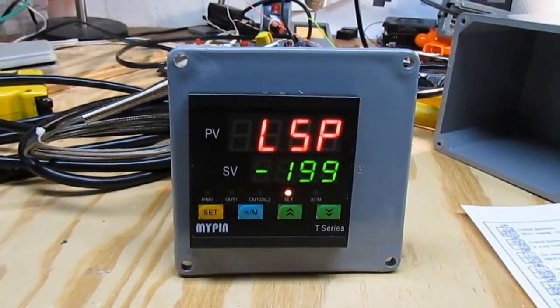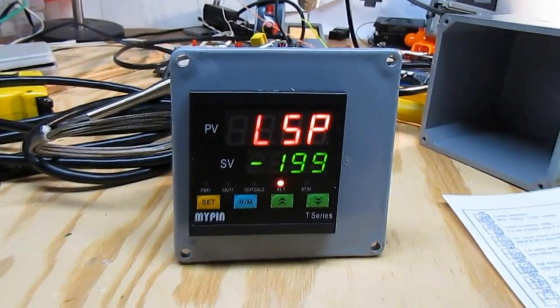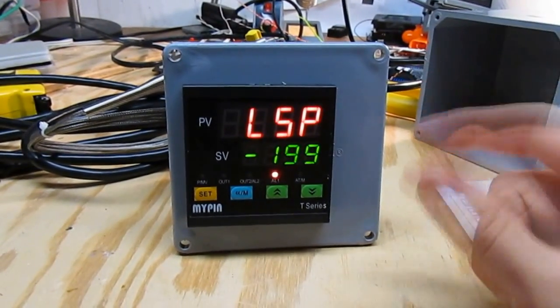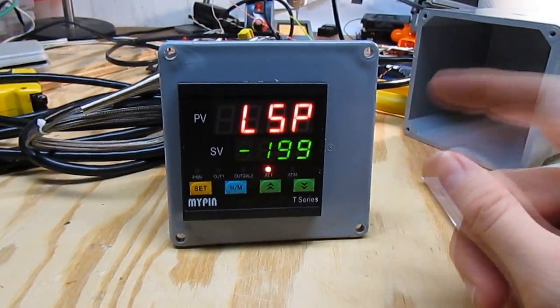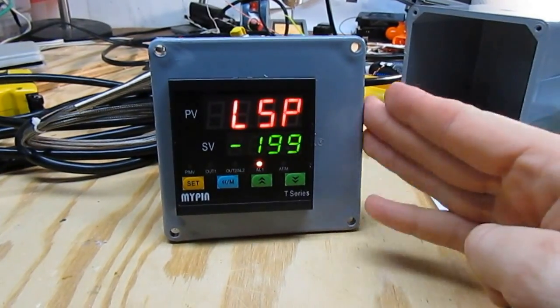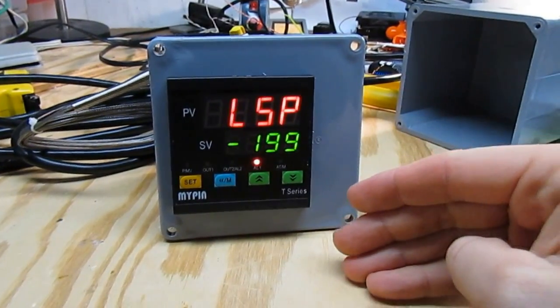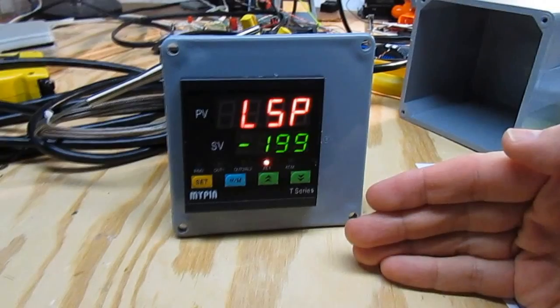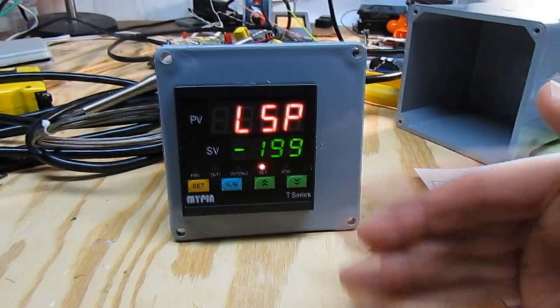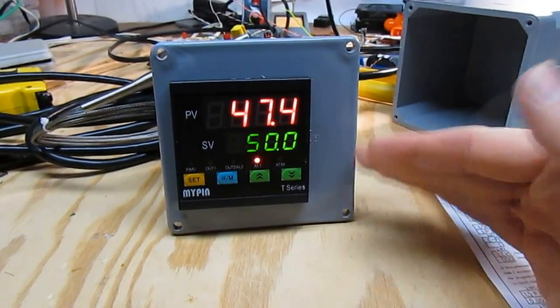I don't remember exactly, but I think this is the area where you turn off the brain. It had some of the PID features that make it kind of flick on and off, flick on and off to slowly bring temperatures into position. You don't want that when you have a compressor running. You want to run the compressor for a period of time and then shut it off.